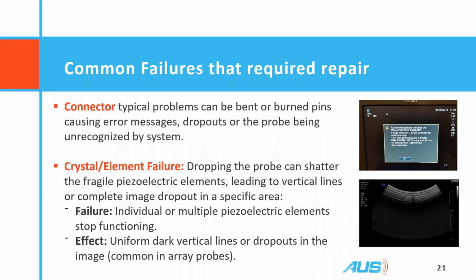Once you determine that it is probe related, it's really in your best interest to get it sent in for evaluation. A lot of sonographers may tell you that if the artifact is off to the left or the edge of the image, it's not important.